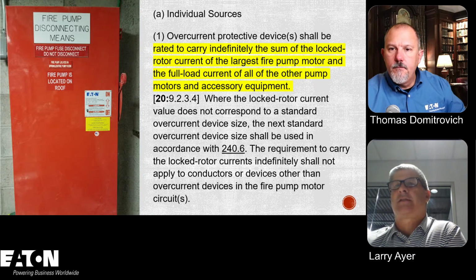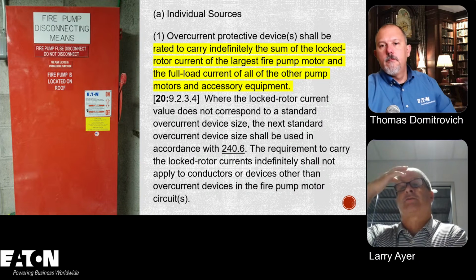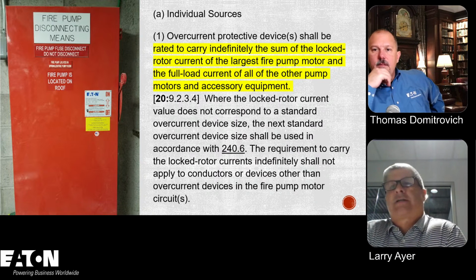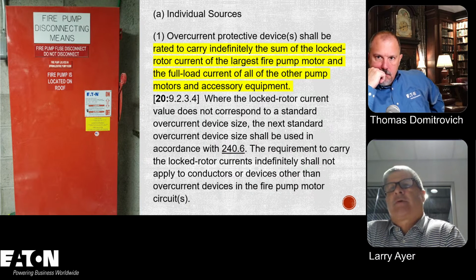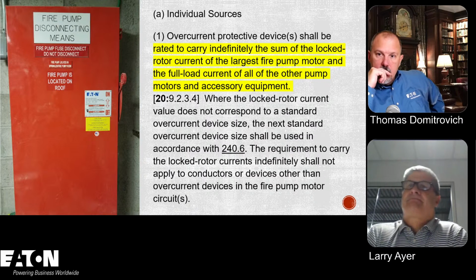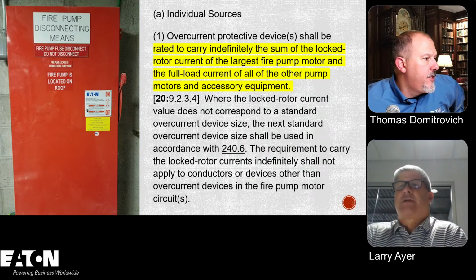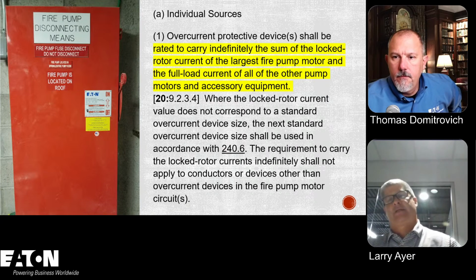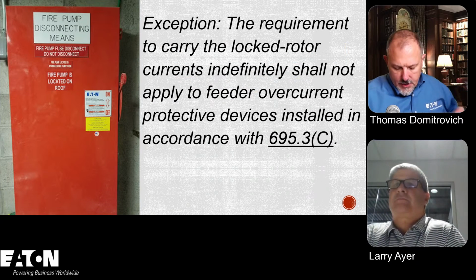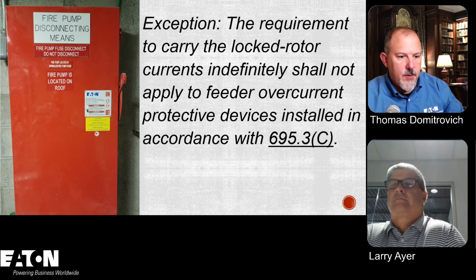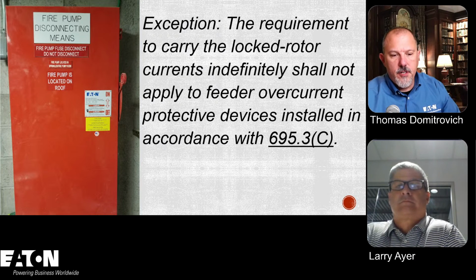And so this is the main requirement for an individual source. Overcurrent protective devices shall be rated to carry indefinitely the sum of the locked rotor current of the largest fire pump motor and the full load current of all the other pump motors and accessory equipment. Yep. And that's where the 6 times comes in. Yeah, and that's what Bruce is saying. It's important to mention that the overcurrent device is 600%, but the wire only has to be 125%.